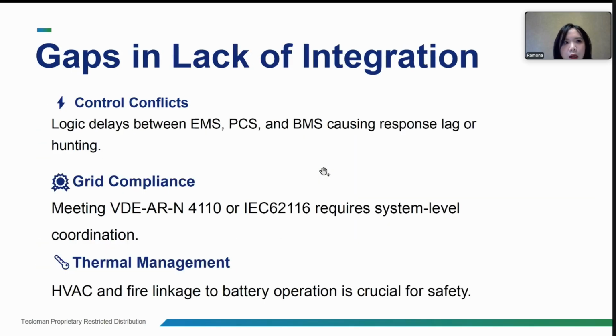So what problems come from poor integration? There are three major areas. First, control conflicts. The EMS, PCS, and BMS must communicate extremely fast, sometimes even milliseconds matter a lot. If communication delays happen, the system response becomes unstable. The system keeps adjusting and over-adjusting again and again. Finally, the grid becomes unstable and equipment wear increases.